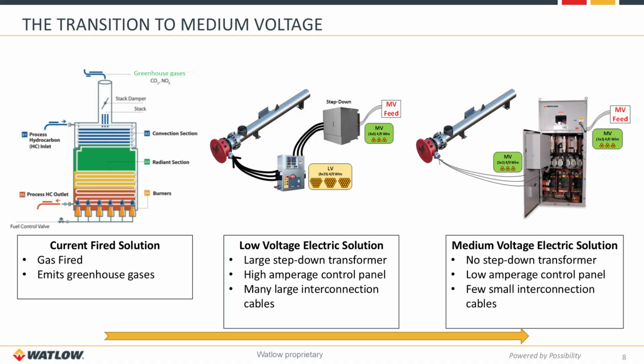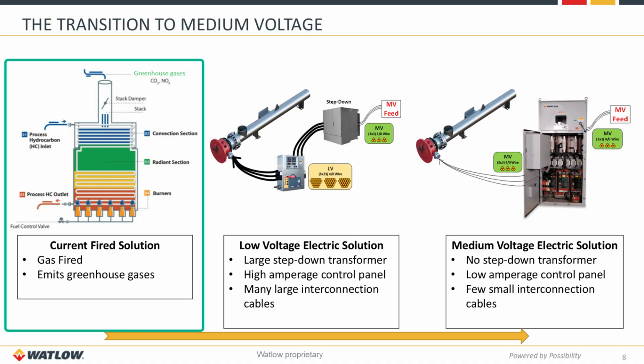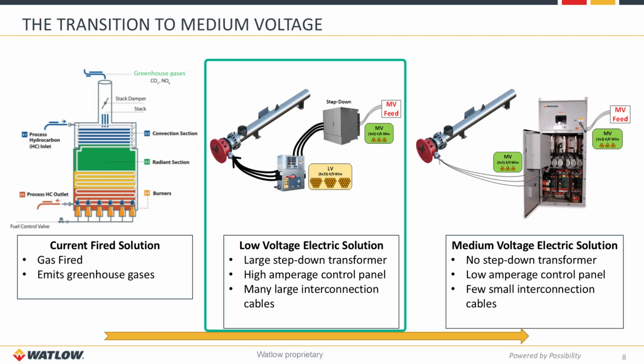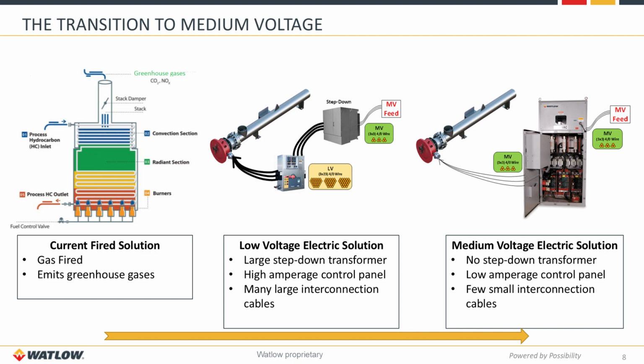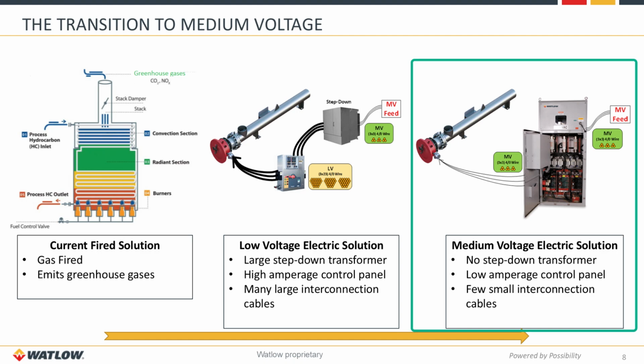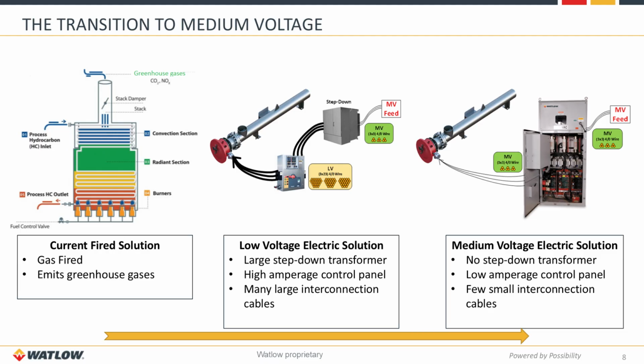How are industrial heating solutions evolving? The current fired solution is typically gas-fired and emits greenhouse gases. The low voltage electric solution requires step-down transformers, high amperage panels, and lots of cabling, as shown in the graphic just above. For the medium voltage electric solution, we're able to eliminate those step-down transformers, use low amperage panels, and require significantly fewer and smaller cables. Medium voltage integration dramatically simplifies installations and improves efficiency for multi-megawatt heating applications.